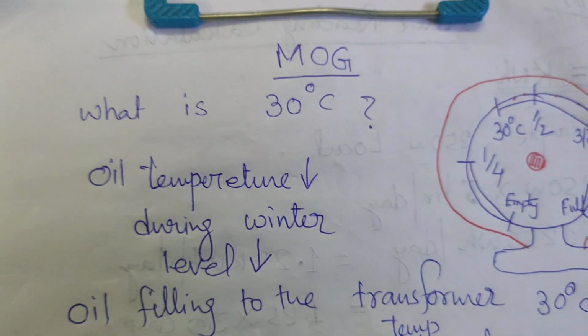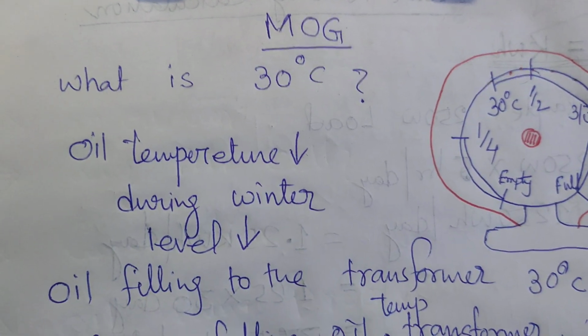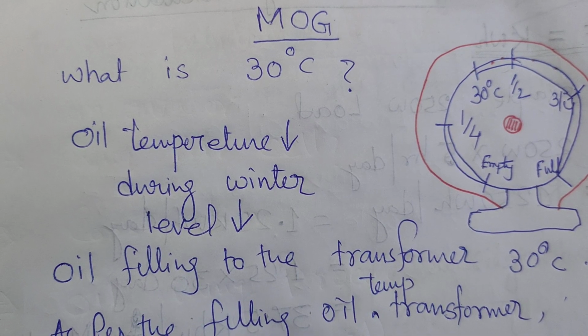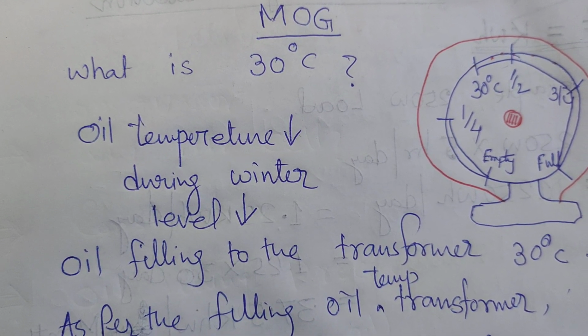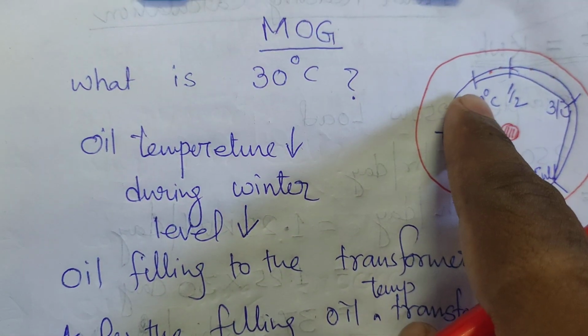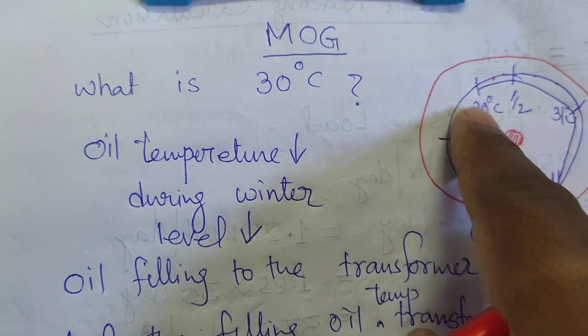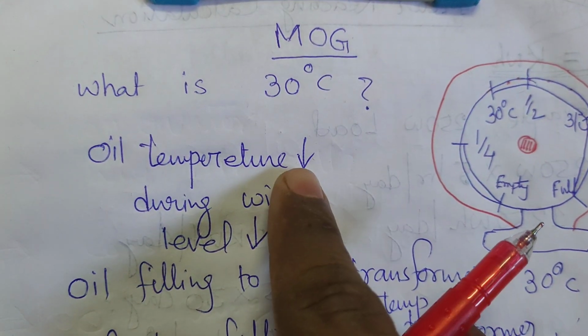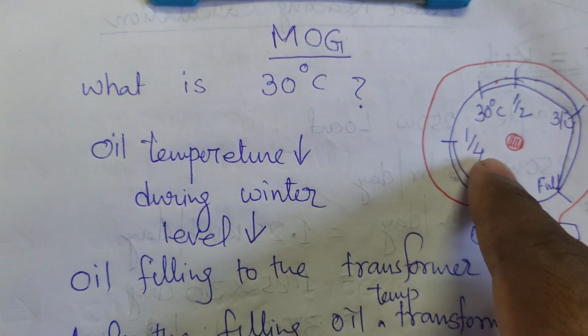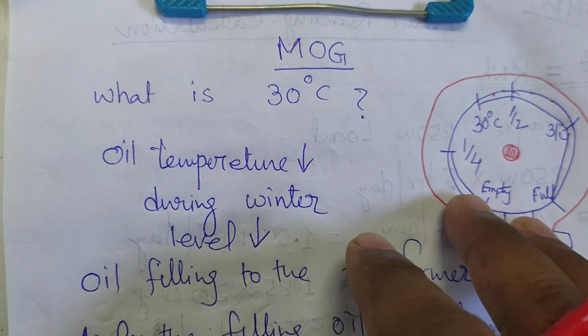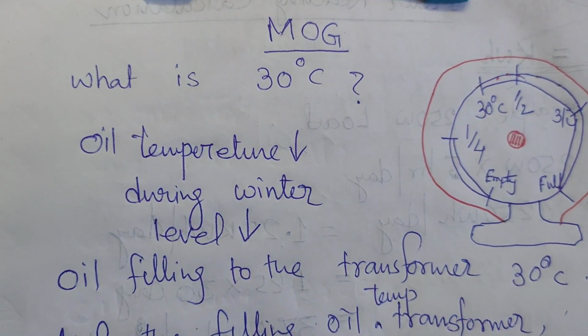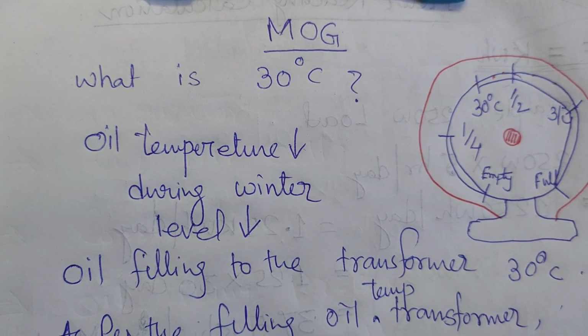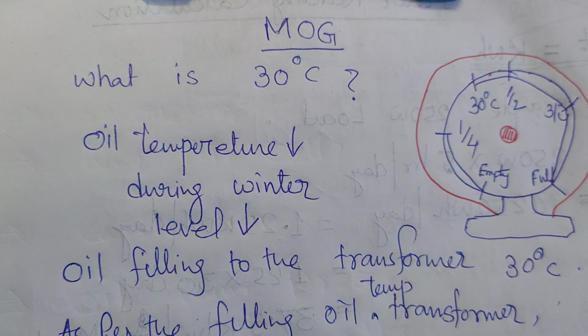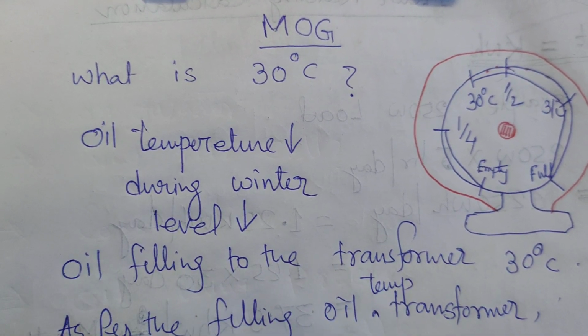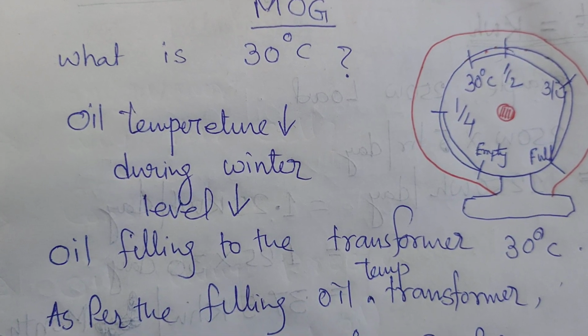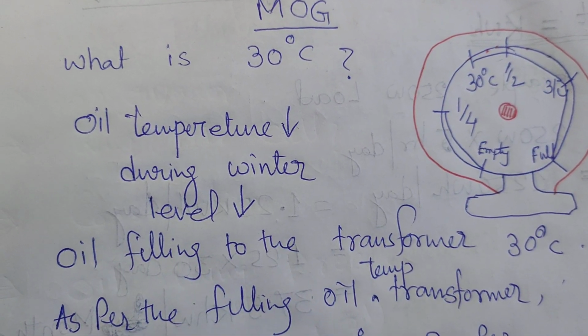So it is very important, and that's why it is 30 degrees Celsius, because as per the design calculation and our scientific procedures, if the oil level is up to this point, that means the temperature of the transformer oil is 30 degrees. If the oil temperature goes down during the winter, the level of the oil goes down. So the temperature goes down, and there is oil expansion and contraction. Expansion happens during the summer season, during overloading, and during the heating effect, the oil expands, and during the cooling effect, the oil contracts. Expansion and contraction are properties of the oil.